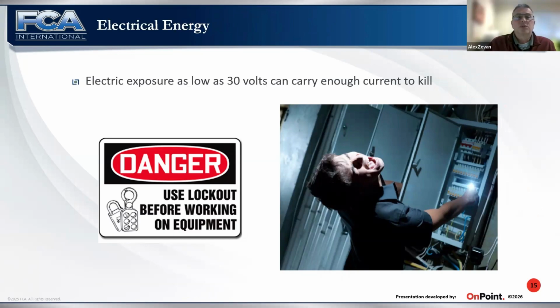Low voltage is something that needs to be expressed, because we can't think that just because it's low voltage, it cannot affect us. One thing that makes low voltage very dangerous is that when we have lowered resistance in our body, or we're sweaty or wet, this allows the low voltage system to deliver lethal currents through our body. The story goes that there was a cleanup crew performing work inside a renovation area, using a 24 to 30 volt LED temporary lighting system powered by a step-down transformer.